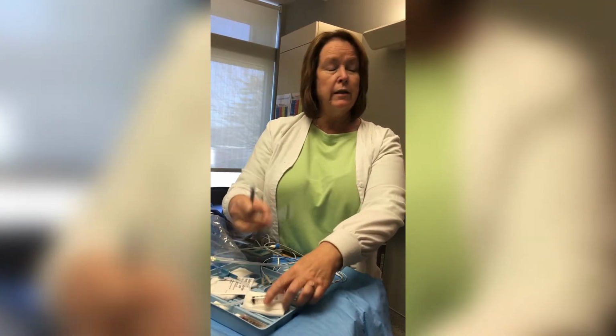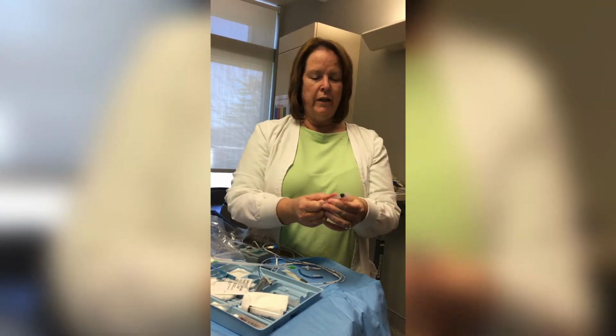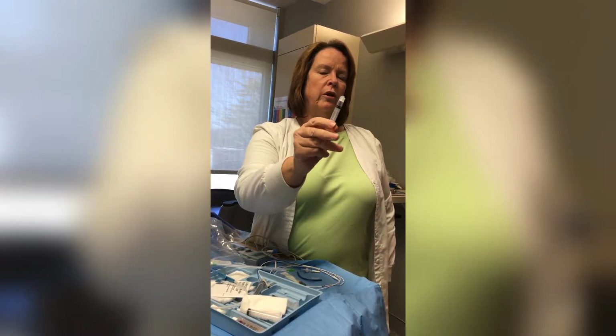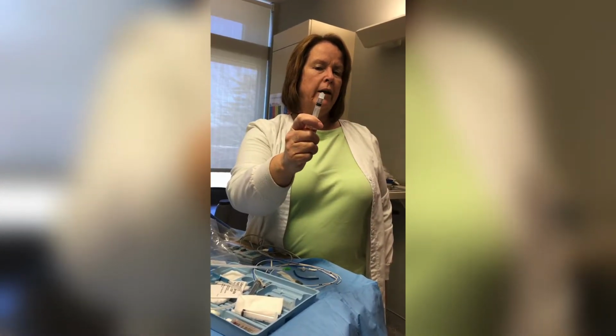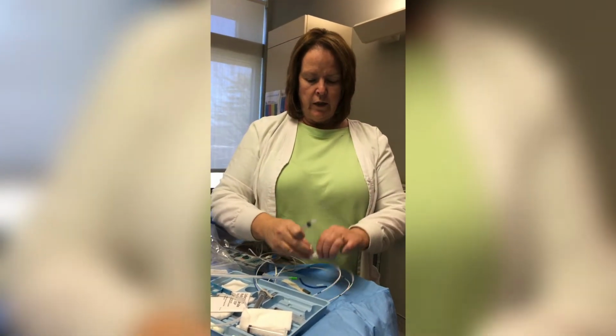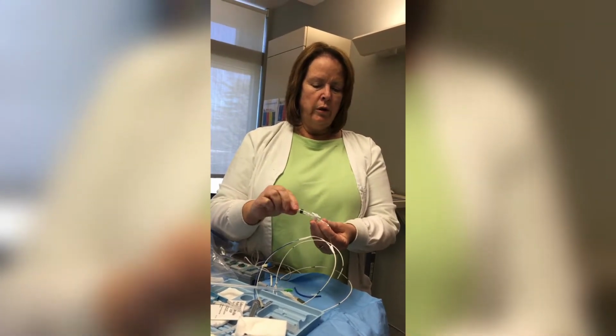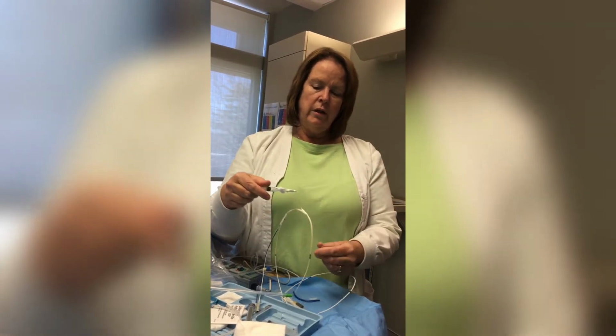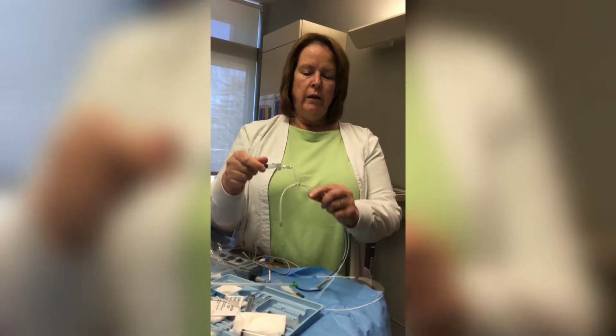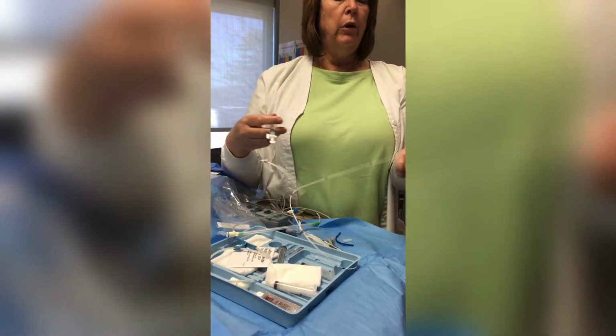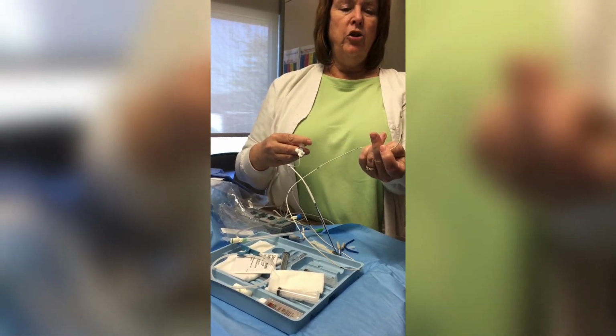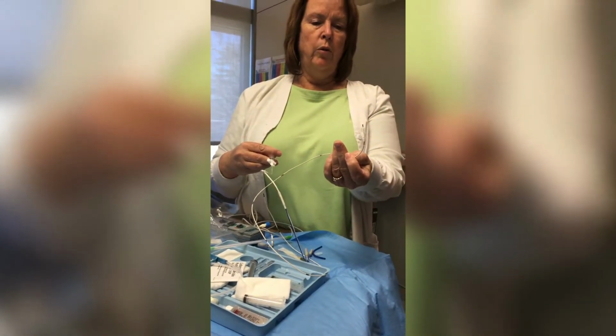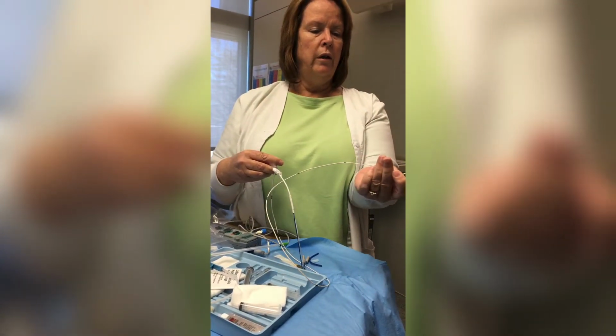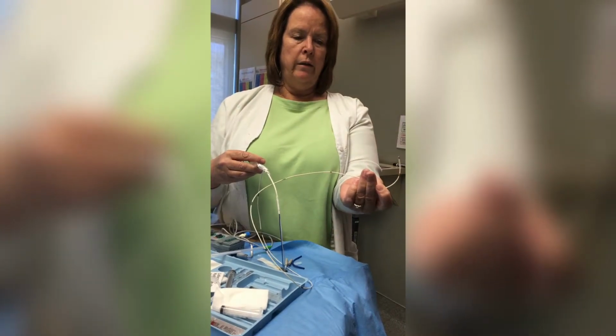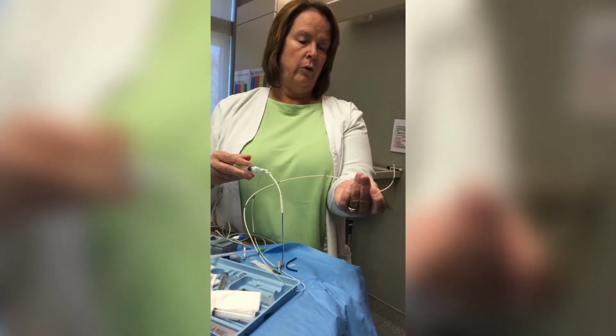Oh, this little syringe that the doctor will hand to you only measures a certain amount of air. It cannot pull back anything more than what is needed. So what you will do is screw it onto the end here, and at the end of the pacemaker there will be a balloon. So look at the tip, and as I inject air, the balloon should be opening up. Can you see the balloon there? And then we're going to let the syringe go back, and the air goes out of the balloon.